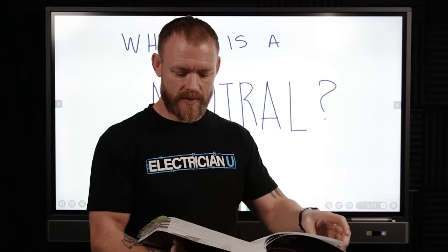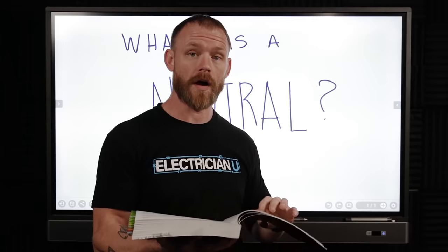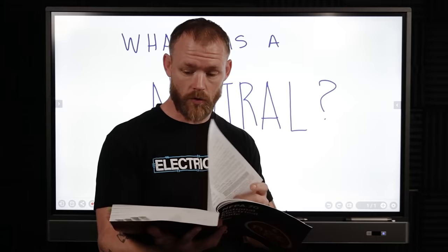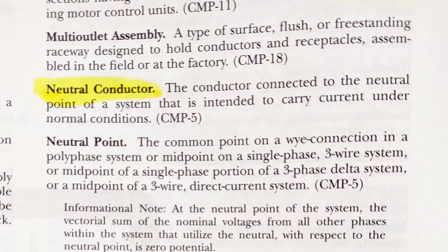The first thing I think is a good idea is to look at Article 100 of the National Electric Code. We're in the 2020 code book. What do they consider a neutral? More specifically, neutral conductor. It says the conductor connected to the neutral point of a system that is intended to carry current under normal conditions.